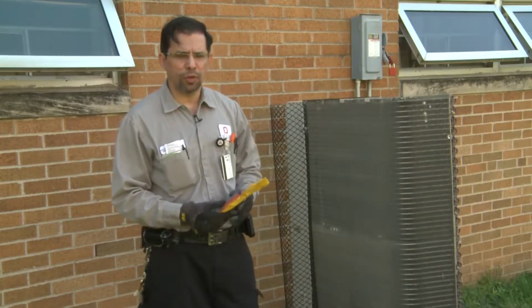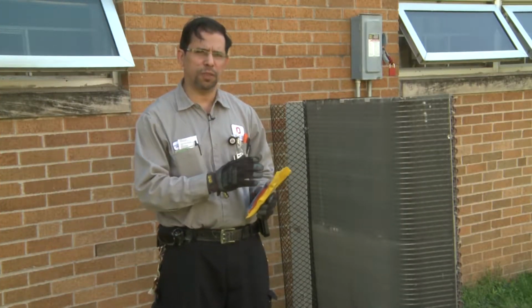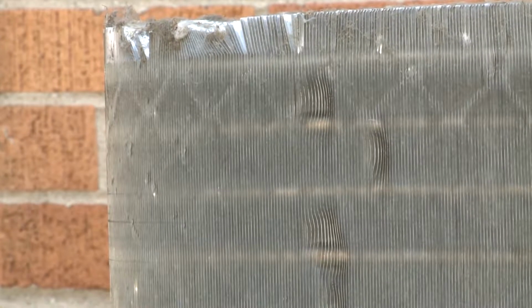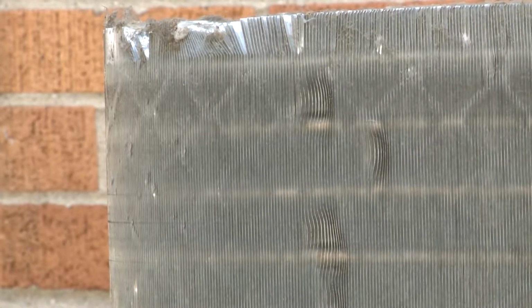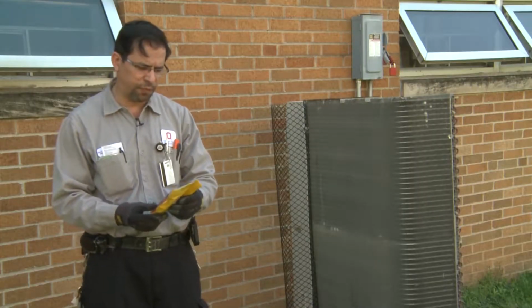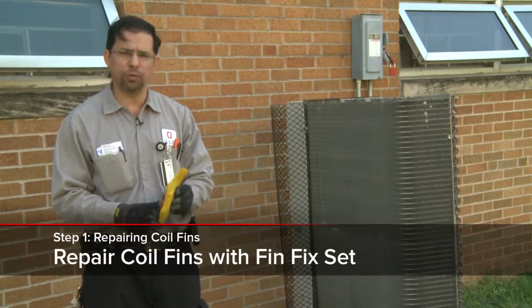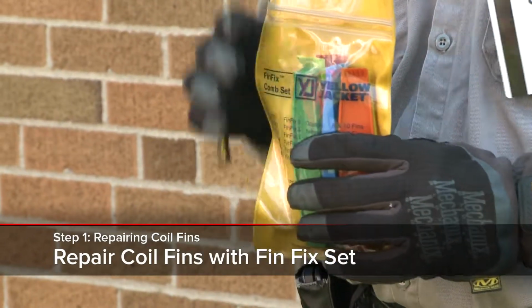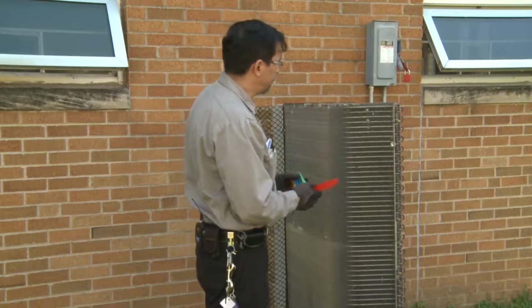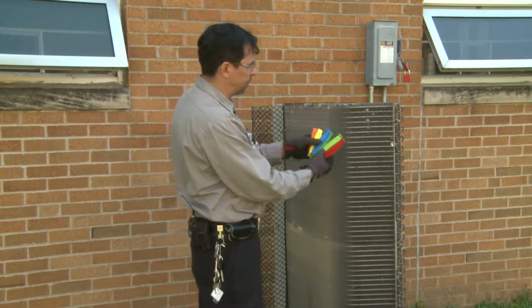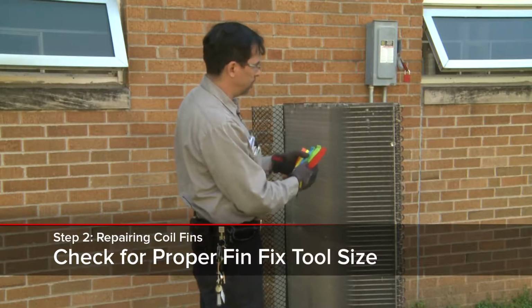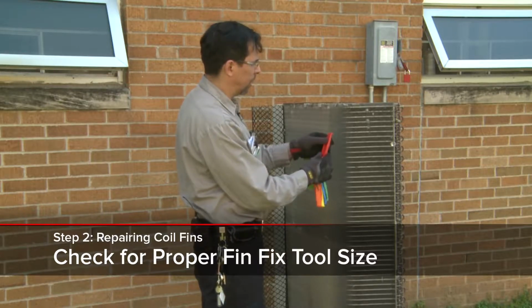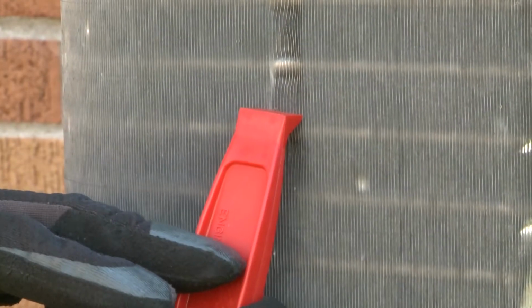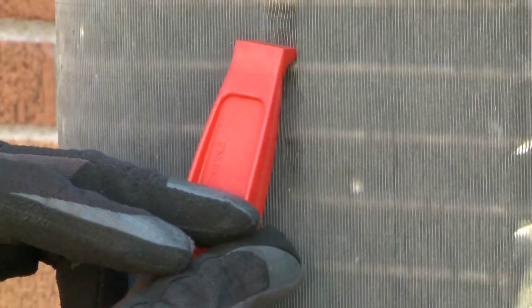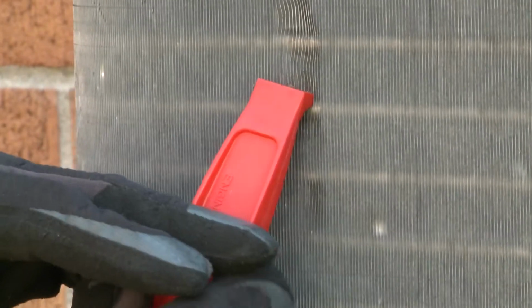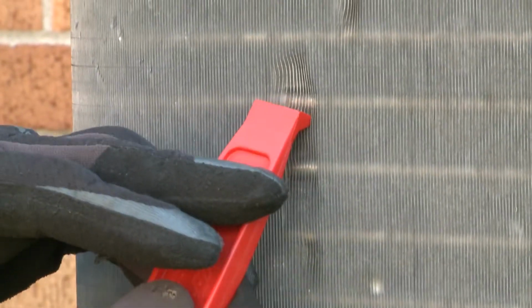Before we proceed to clean the coil, we do a quick inspection of the condition of the fins in the coil, and we sometimes bump into issues with the fins in the coils. So to correct those problems, we have this fin fix combo set here, and we can use these to actually fix the fins that have been bent. In this particular case, I have different sizes, different fins for these coils. So I'm going to try to match the one that will allow me to execute the job properly. So in this case, I'm just going to go there and then straighten them up just like that. Then all the way up.